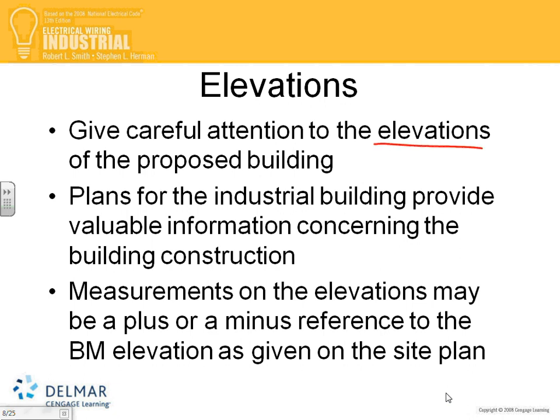Elevations, guys, elevation is a big deal for us - thank God in the project you guys have, ours is 3D. The most important thing in elevation, especially in an industrial project, guys, is because we're going to have bus ducts. Bus ducts are big, guys - you're looking at probably 8 inches by 8 inches, a big duct going all the way. That's a big chunk of thing to move 50 feet in the building. That's where elevation becomes a big deal, guys. Then you have to coordinate between you and all other disciplines. I can't go through a beam, I can't go through a duct. So elevation becomes a big deal, guys, for us.